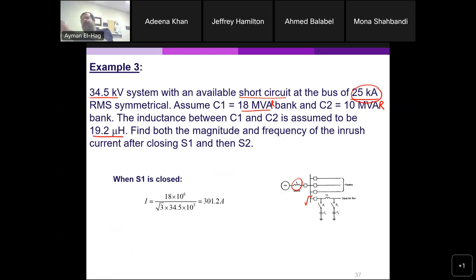This is very similar to the previous example. So we will have here the 18 MVAR, this is your Q, divided by root 3 times the line-to-line voltage, and you will get the line current. This is your line current I. Now your XC, the reactance of the capacitor, is the phase voltage divided by this current, and you will get 66.13. When we divide the voltage by root 3, you get the phase voltage across the capacitor. And then divide by its current, and you will get the reactance.